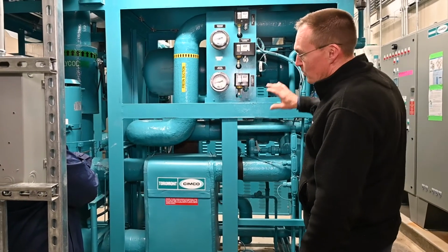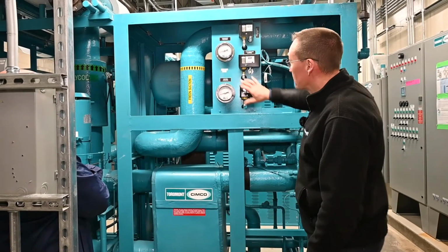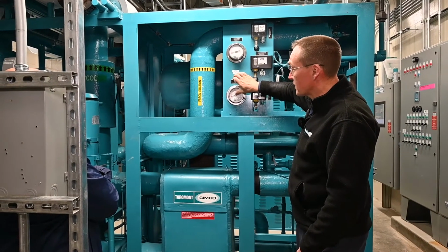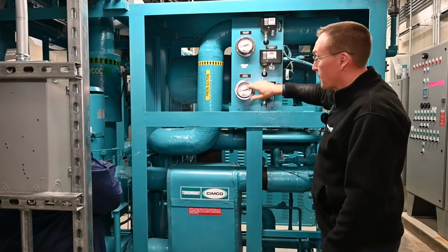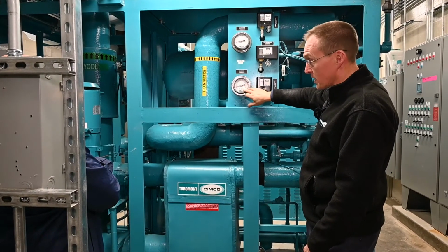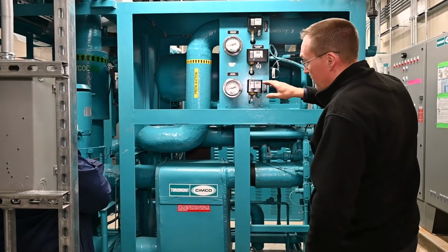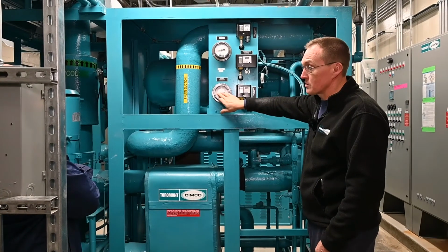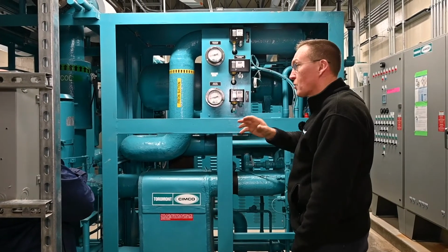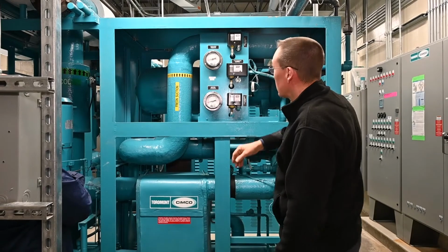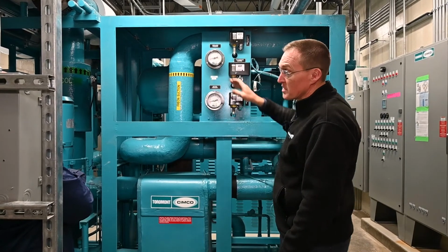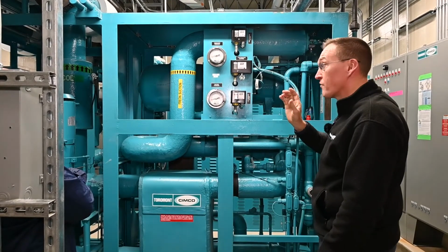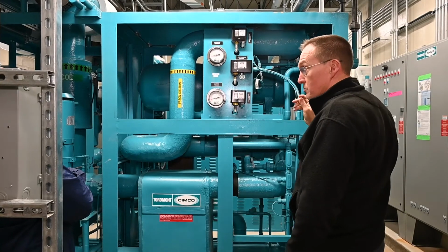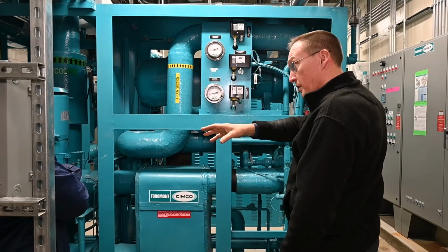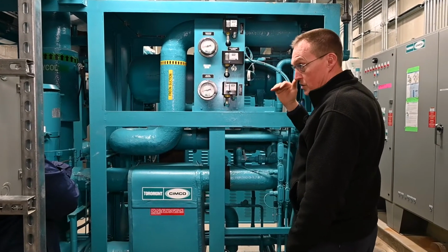So what you're going to see once the panel covers go on this unit, you're still going to be able to see your suction pressure gauge and your discharge pressure gauge. Nominal pressures, when the system is running, you're going to see anywhere between about 11 psi on the suction down to 3 psi, depending on how cold your glycol gets. Okay? Discharge is always going to be targeted at about 150 to 140. That's what the computer is going to cycle all your other pumps to maintain.